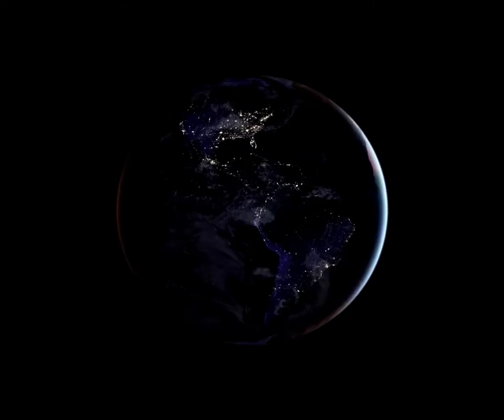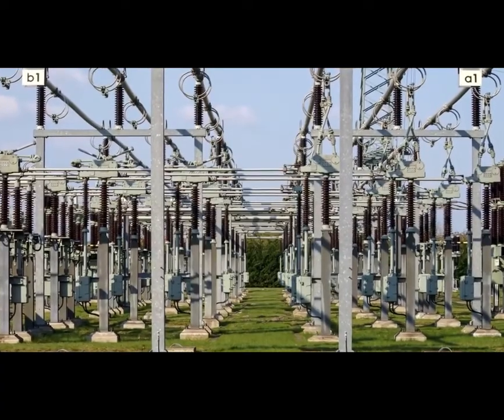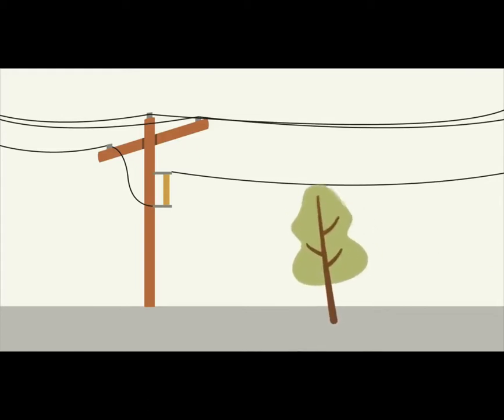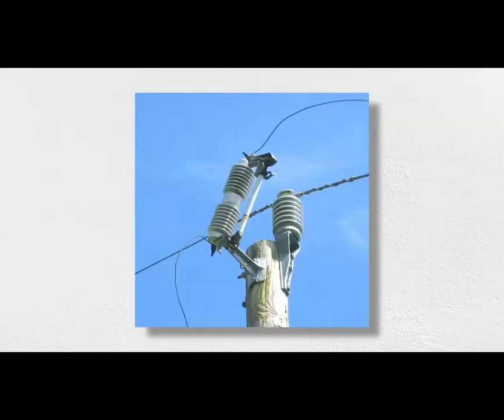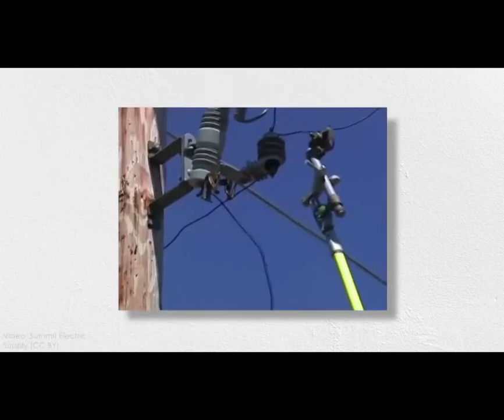Because of the overwhelming complexity of the power grid, faults can and do cascade in unexpected and sometimes uncontrollable ways, leaving huge populations without power for hours or days. Many of the ways we protect equipment from faults are handled at a substation. The most common type is a short circuit to ground, which creates a low resistance path for current and leads to overload. The simplest protection is a fuse — a device that physically burns out at a certain current threshold. Fuses are dead simple and don't require much maintenance, but they are one-time use and can't interrupt current for other types of faults.